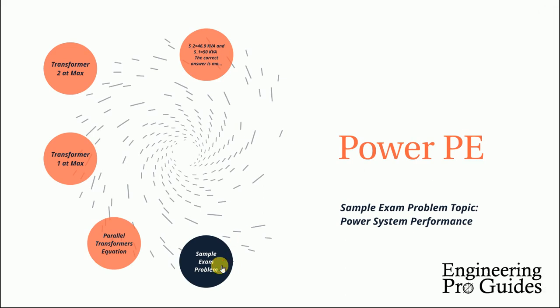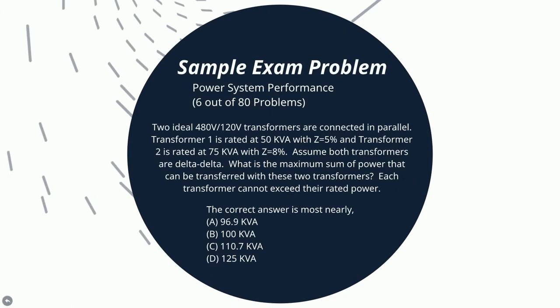The question reads: two ideal 480 volt, 120 volt transformers are connected in parallel. Transformer 1 is rated at 50 kVA with an impedance of Z equal to 5%, and Transformer 2 is rated at 75 kVA with Z equal to 8%. Assume both transformers are delta-delta. What is the maximum sum of power that can be transferred with these two transformers? Each transformer cannot exceed their rated power.